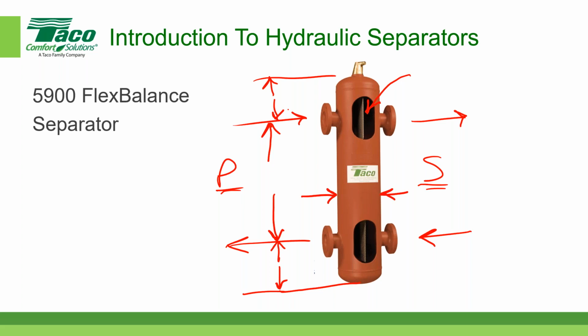So the advantage to having a pre-designed thing is that there's no guesswork involved. You just basically pipe it up, you put it into the proper primary, secondary piping arrangement like we had over here. Again, this is primary. Let's put in here on the primary side, let's put out over here. And then on the secondary side, let's put in the bottom and out at the top. Okay. As long as you just connect the piping and it's the right size, then the hydraulic separator works.